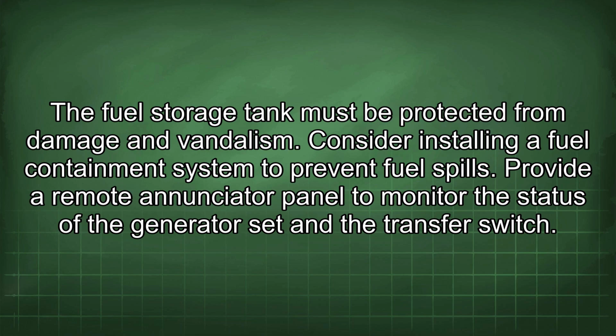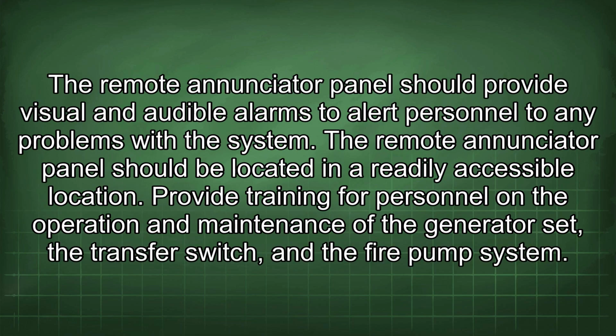Provide a remote annunciator panel to monitor the status of the generator set and the transfer switch. The remote annunciator panel should provide visual and audible alarms to alert personnel to any problems with the system. The remote annunciator panel should be located in a readily accessible location.